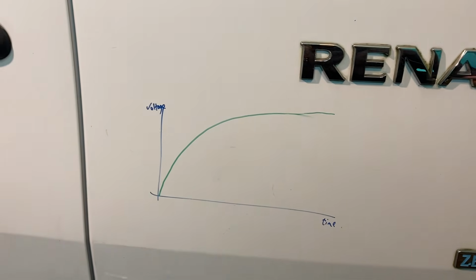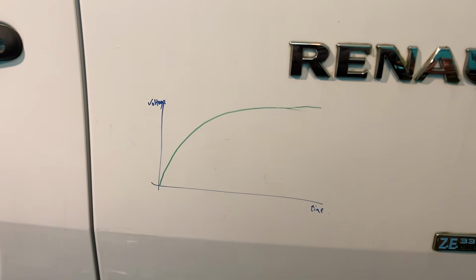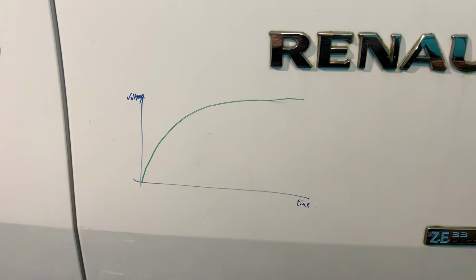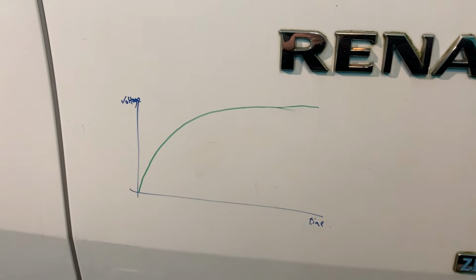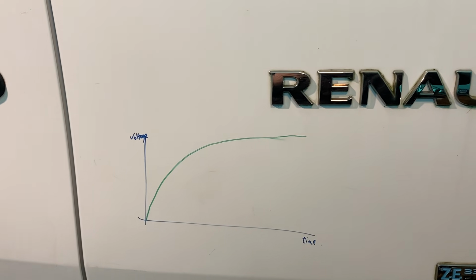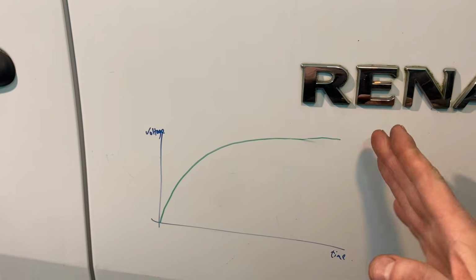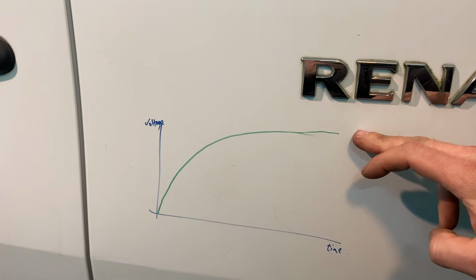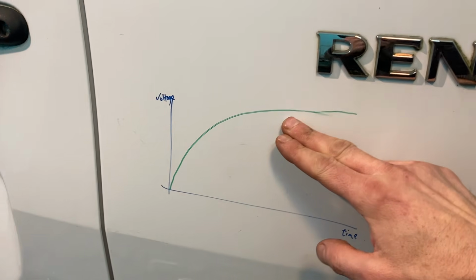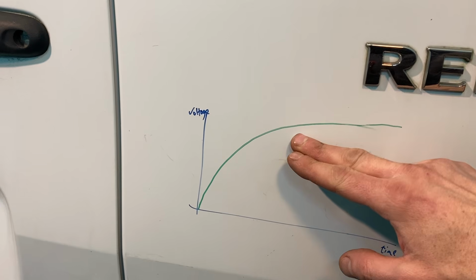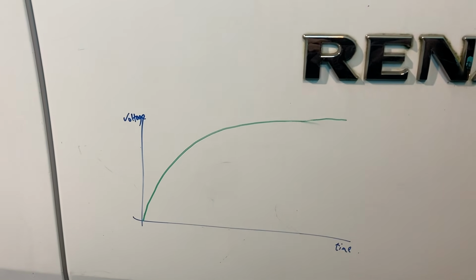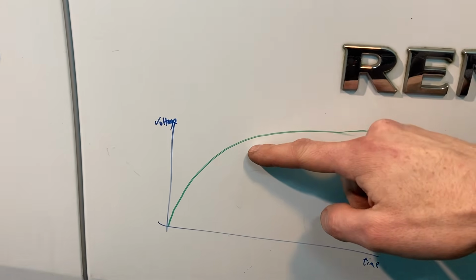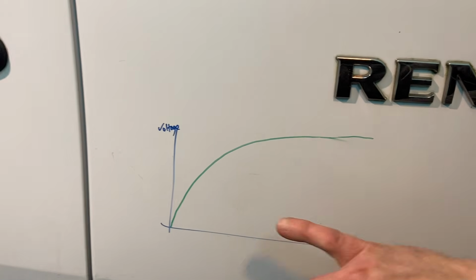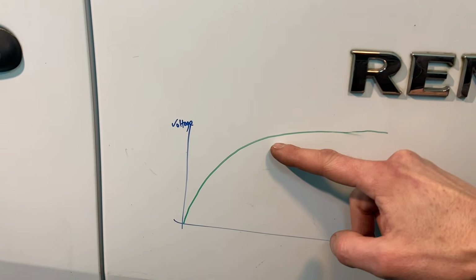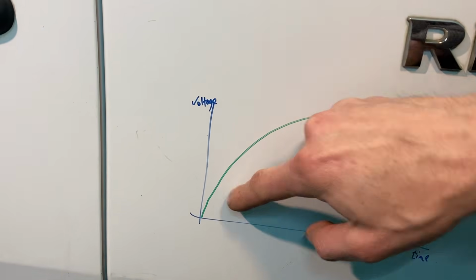So what normally happens when you've got a weak cell - one that has less capacity than the others because it's old and suffered more - is: let's say they're all full, right up here, and you drain them a bit and not a lot happens. Then you drain them a bit more, but because one has lower capacity, it reaches its cliff, its steep bit of the curve, sooner. So at a lower state of charge, the weaker ones become more apparent because they start to fall off this cliff.